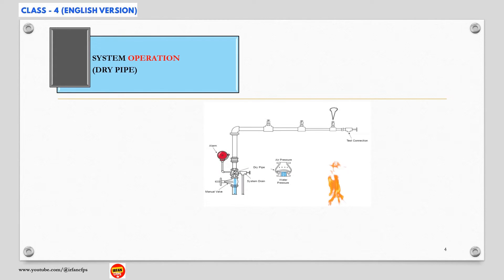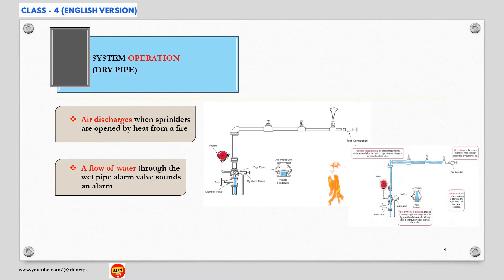However, in this case, water isn't immediately available because the pipe is not water filled. Instead, air is released from the sprinklers that are activated. This creates a drop in pressure causing the dry pipe valve to open and water to fill the system. Water will then flow from the open sprinkler head. A flow of water through the dry pipe valve sounds an alarm.